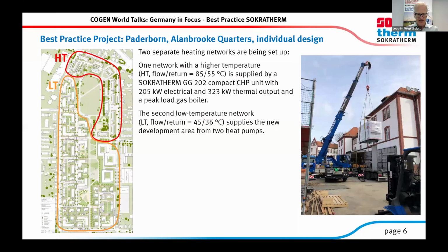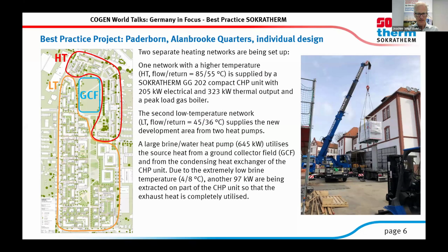The second network is a low temperature network with a flow temperature of 45 degrees, 36 degree return temperature, which supplies the new development area from two heat pumps. The first one is a brine water heat pump with more than 600 kilowatt thermal output, which utilizes the source heat from a ground collector field, shown in the graphics on the left side. And the other heat source is the condensing heat exchanger of the CHP unit.